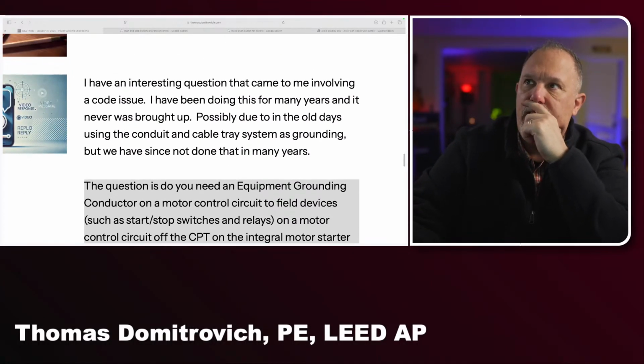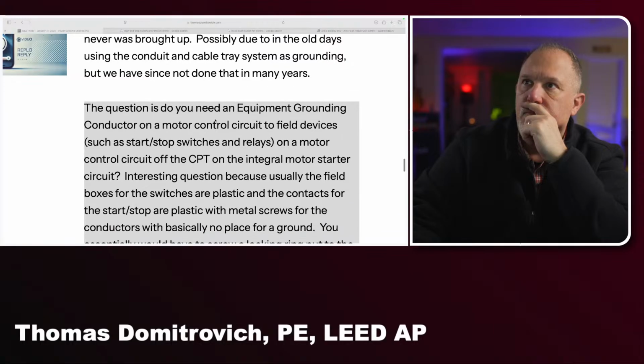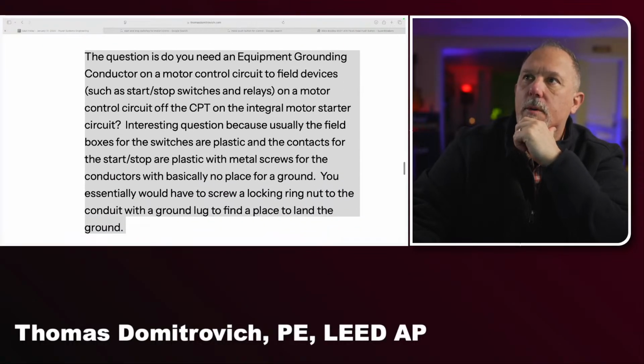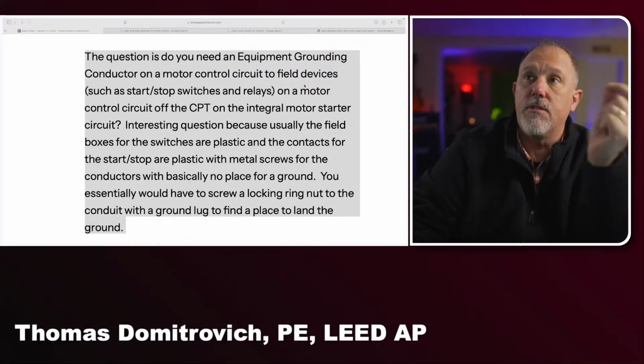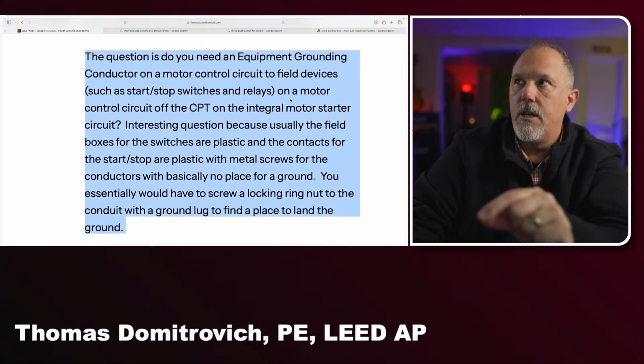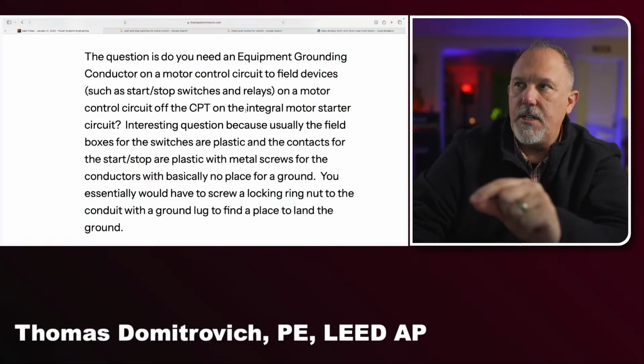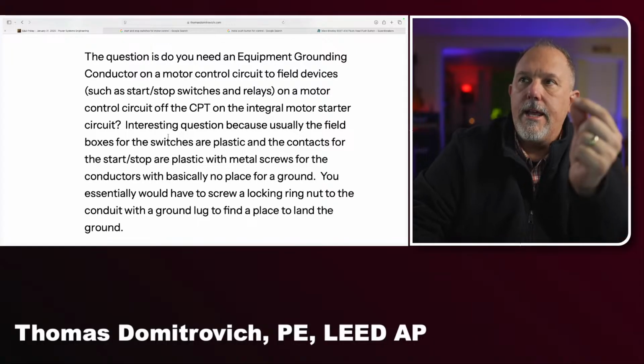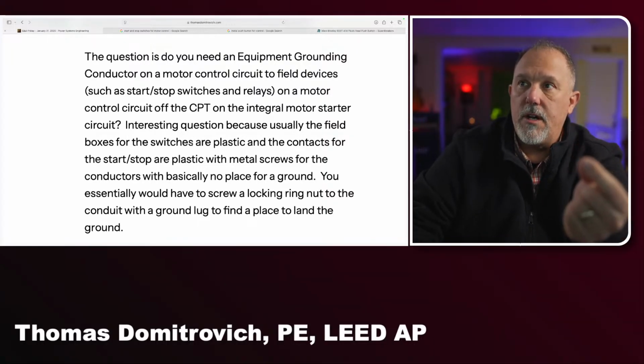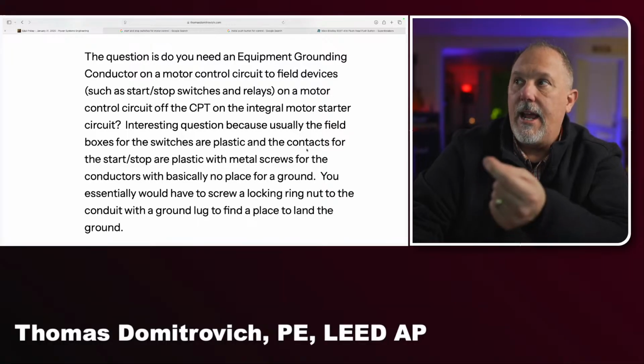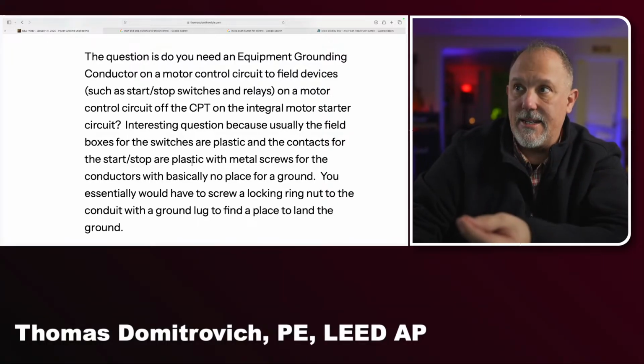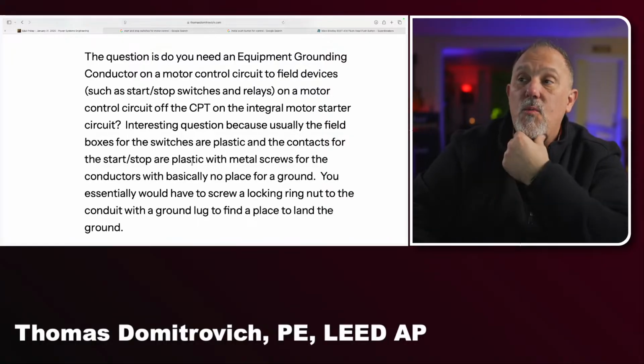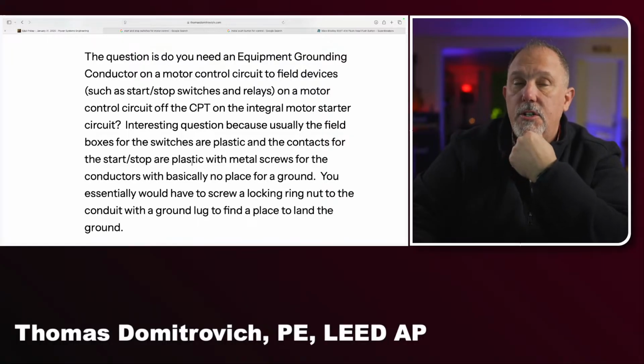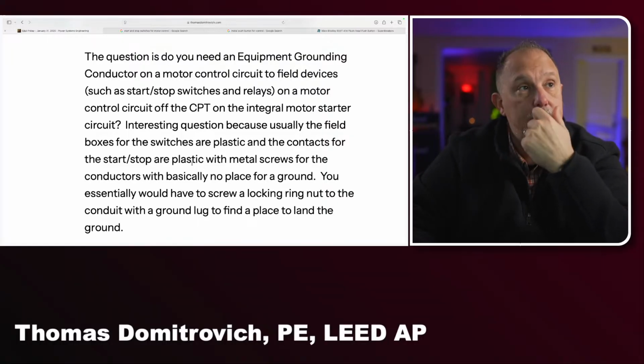When you have an equipment, the question is, do you need an equipment grounding conductor on a motor control circuit to field devices like start and stop relays, on a motor control circuit off the CPT, control power transformer? Interesting question, because usually the field boxes for the switches are plastic and the contacts for the start stop are plastic with metal screws for the conductors with basically no place for a ground. So all of those components are plastic.